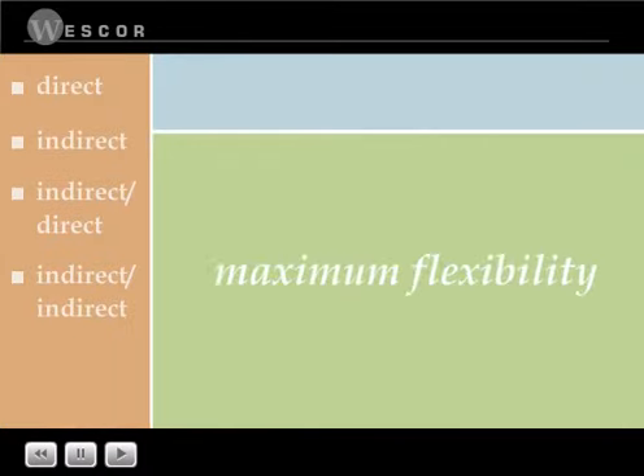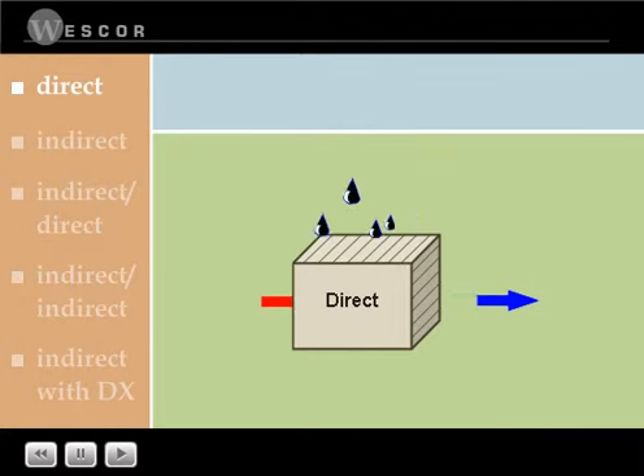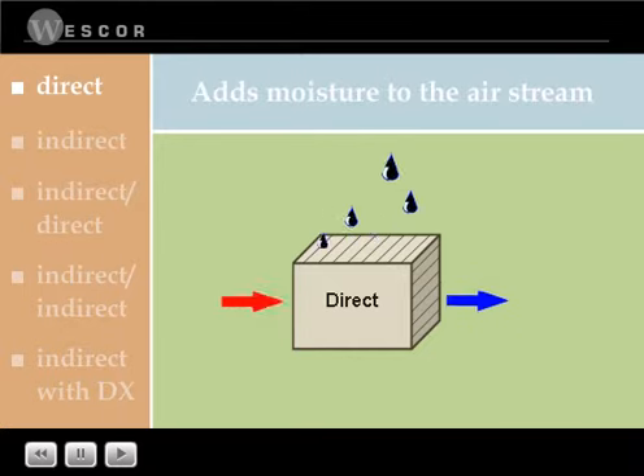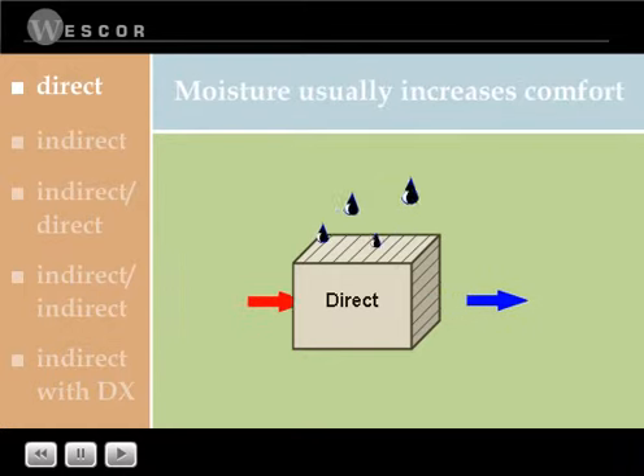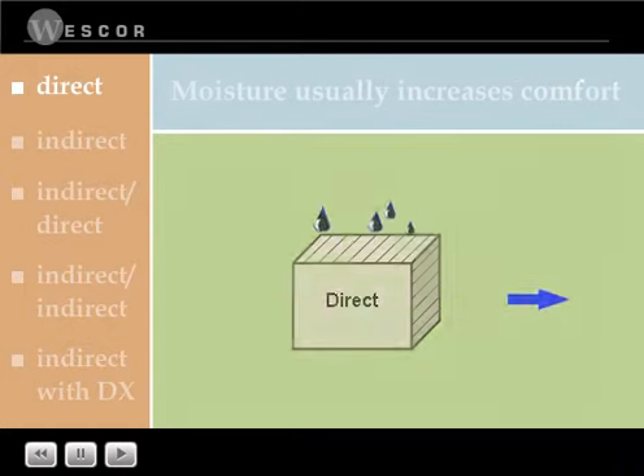This brief video explains how evaporative cooling works and its many benefits. Five varieties of evaporative cooling allow for maximum flexibility. With direct evaporative cooling, outside air is blown through a water-saturated medium, usually cellulose, and cooled by evaporation. Direct evaporative cooling adds moisture to the primary airstream. Because the Pacific Northwest has dry summers, more moisture in the air usually increases comfort.